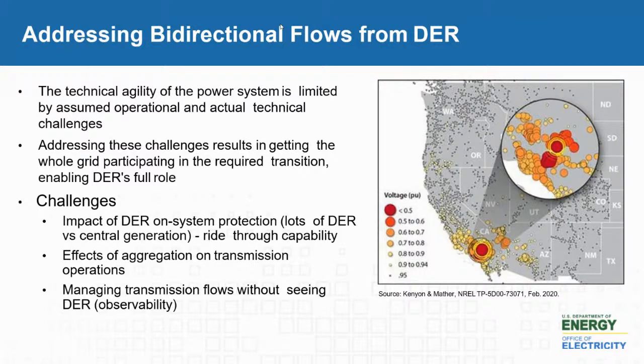The other challenge, which we have already seen happening more than once, is when you have a lot of solar resources and you have a fault, how do you ride through this fault? If inverters see a voltage drop during the fault, they can take themselves offline, which makes the situation even worse. The system will collapse because now you not only have a fault, but you have lost a lot of your generation, so you can't serve all loads. We want to be able to ride through faults. The IEEE standard 1547 is addressing those issues.